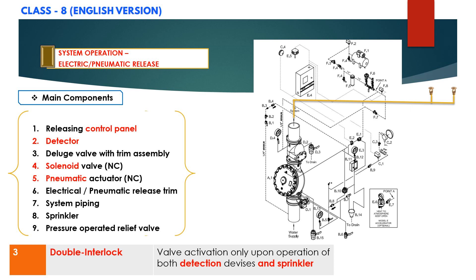In set conditions, the system water supply pressure enters into the priming chamber of the deluge valve through 1 by 4 inch or 8 mm priming line, which includes a normally open priming valve B1, strainer B2, restricted orifice B3, and a check valve.